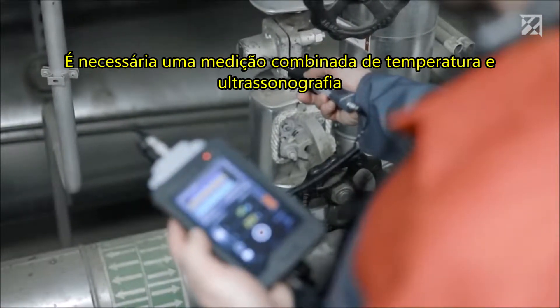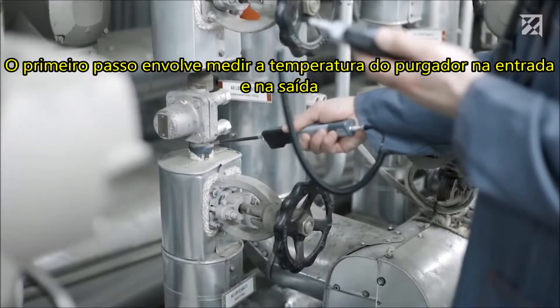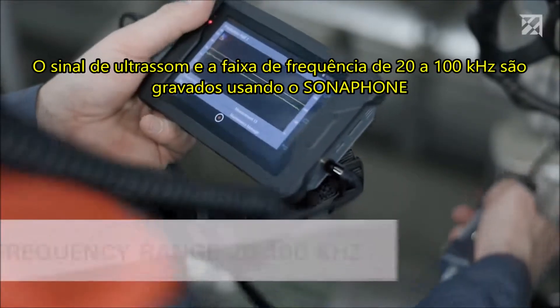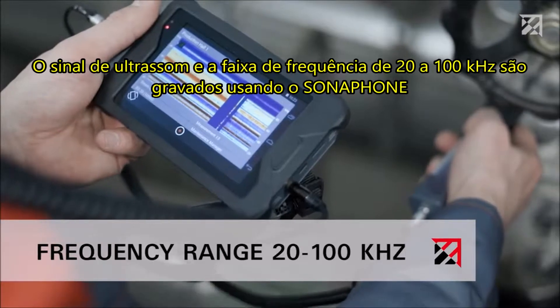The first step involves measuring the temperature of the steam trap at the inlet and outlet. The ultrasound signal in the frequency range of 20 to 100 kilohertz is then recorded using the Sonaphone.